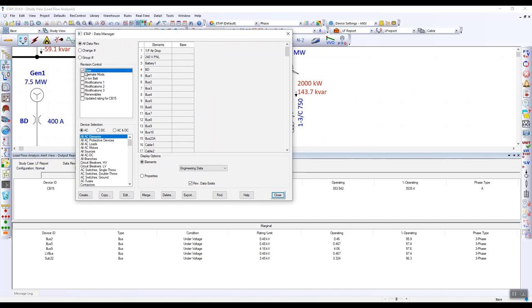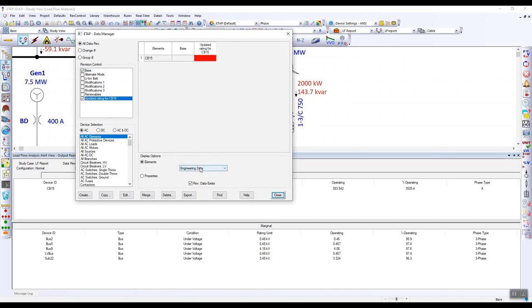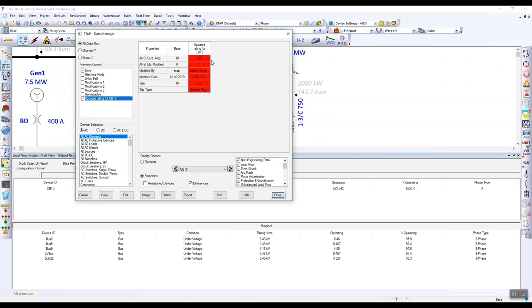I have a preloaded revision where I have updated the size of the overloaded circuit breaker when we first ran load flow. On the left-hand side, we see all the revisions that were made for this project. I'm going to select base, and I'm going to select the updated setting for circuit breaker 15. If we wanted to dive deeper, we can see the exact changes that were made by selecting properties. And in here, we can see that I increased the frame size and also the continuous current for this device.